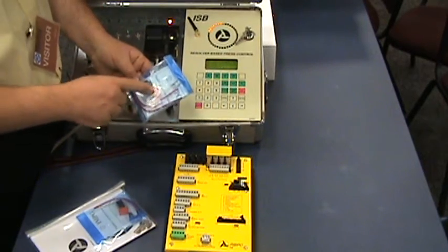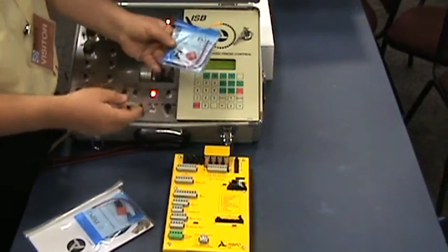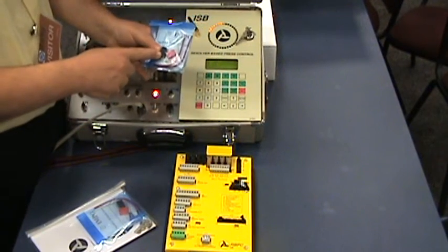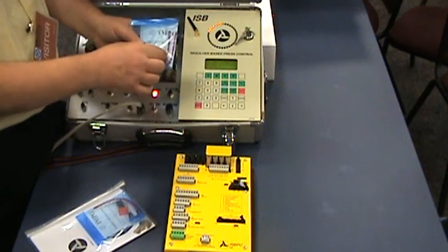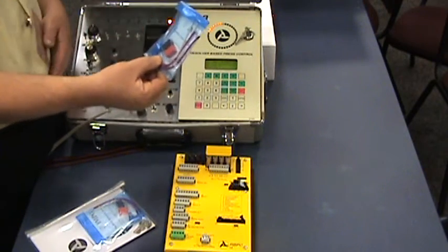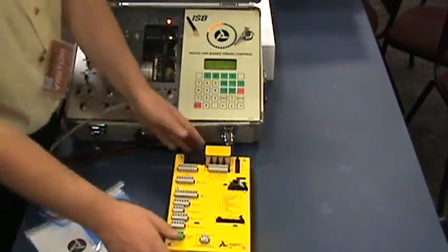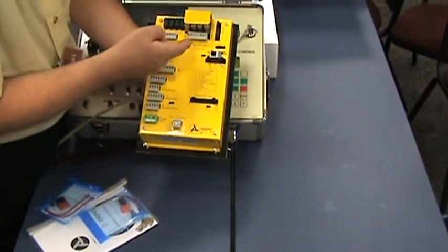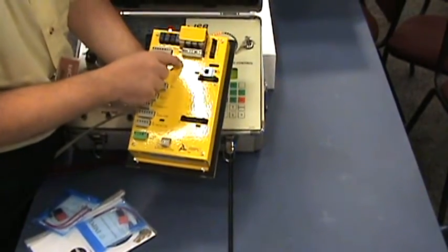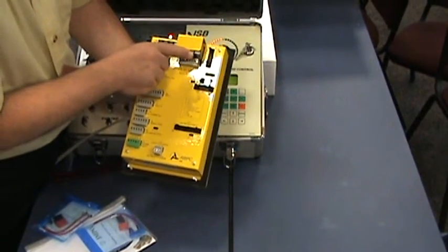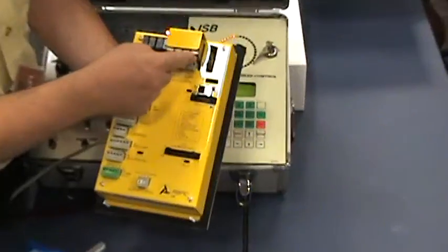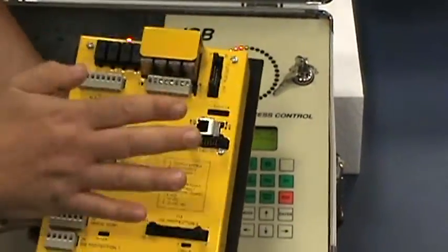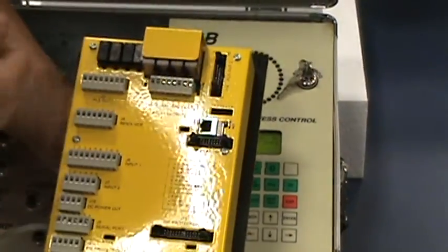And also, we're supplying two small devices, a red and a black device. These are solid state relays. Now, these have nothing to do with the safety valve but they happen to be in the same little envelope. If you look at the back of the RBPC, I identified these four relays. Safety relay one, safety relay two, which are outputs. There's a fault relay in here and there's a mute relay. This is all to do with the light curtain mute and these two are controlling the safety valve.